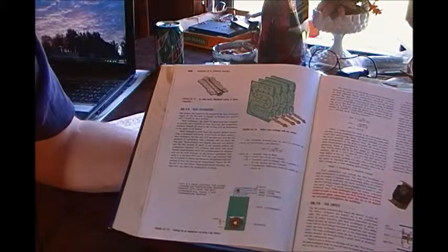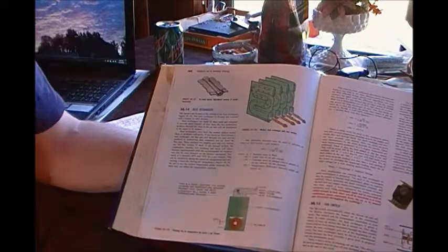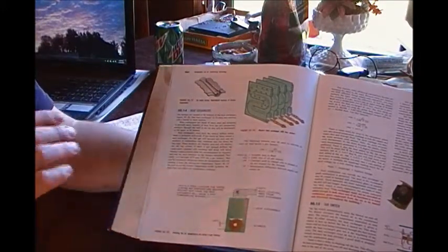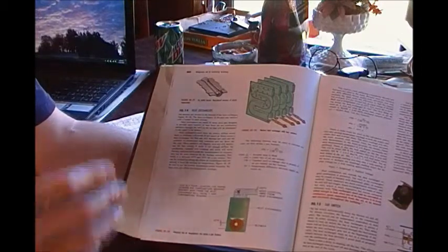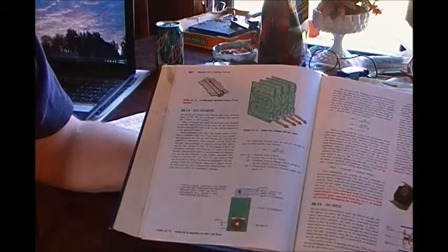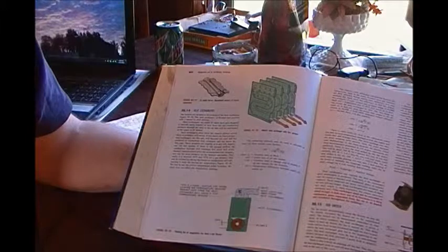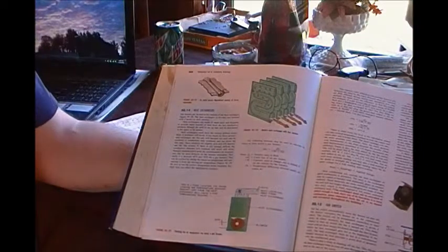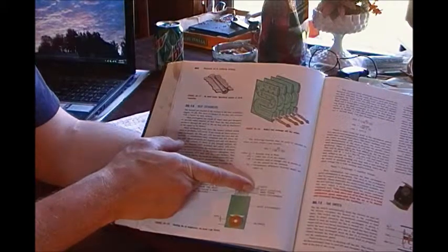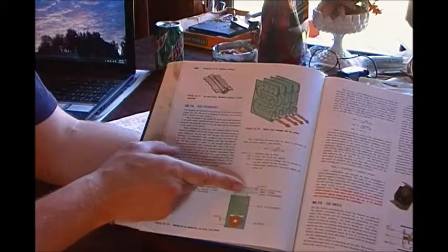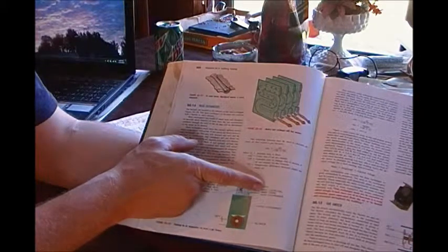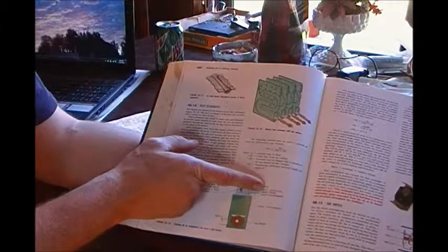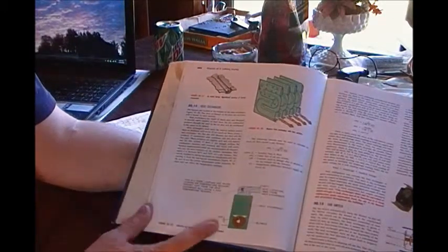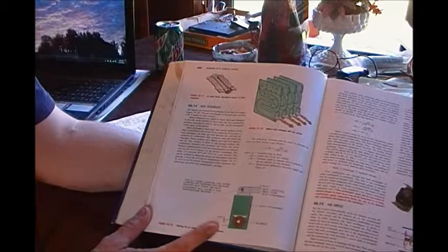So once you have adjusted your fan speed motor to match the differential to get it between 40 and 70 degrees, then you're good. So it's not only gas pressure, we also got to get the right amount of air going over that coil. And we want to make sure we got our thermometers in the right spot so we don't get false readings. At least 3 feet away from the heat exchanger in the supply ductwork. And then your thermometer can go right where your filter is in the boot with the return air.